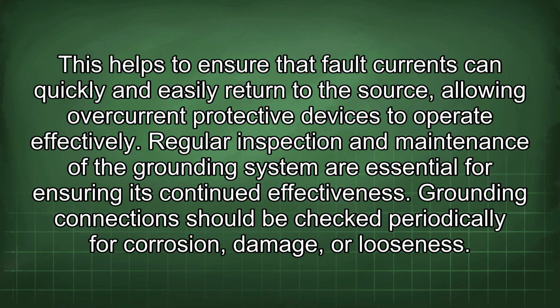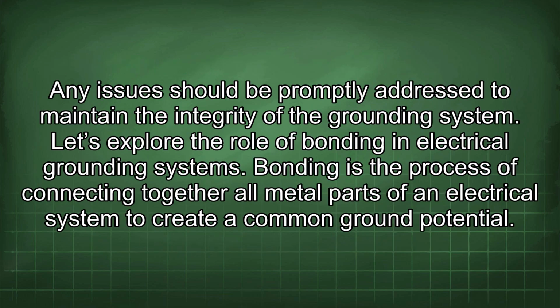operate effectively. Regular inspection and maintenance of the grounding system are essential for ensuring its continued effectiveness. Grounding connections should be checked periodically for corrosion, damage, or looseness. Any issues should be promptly addressed to maintain the integrity of the grounding system.